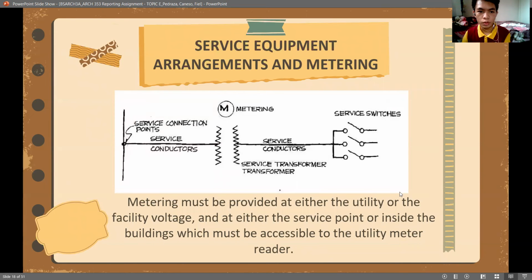Next one is service equipment arrangement and metering. Metering must be provided at either the utility or the facility voltage, and at either the service point or inside the building, which must be accessible to the utility meter reader.